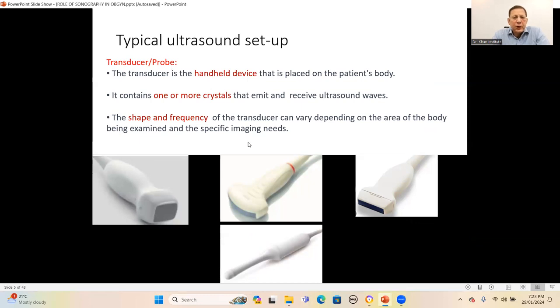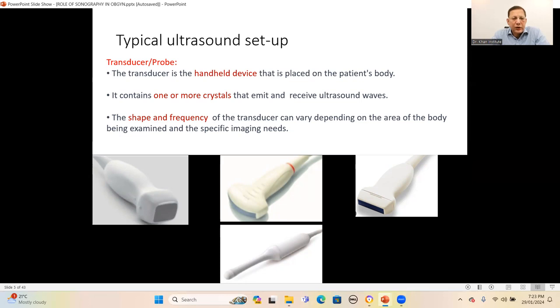The transducer and probe is the basic handheld device used in an ultrasound system. This probe contains many crystals that emit and receive ultrasound waves to perform the imaging. These probes are of different shapes and have different frequencies. The phased-array probe has a very small scan head that can fit in between the intercostal spaces for performing heart studies, which is called echocardiography.